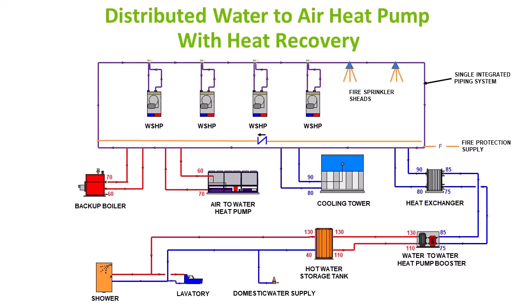But we're also showing here how we can recover heat to heat the domestic water down here in the lower right. So we've got a heat exchanger, a booster heat pump, and now we can recover heat from the HVAC system to heat the domestic water. But we're still using your classic boiler tower up here, and when it gets cold, we need the backup boiler because there's not going to be enough heat generated in the building to heat the exterior, right? Okay, so far so good.